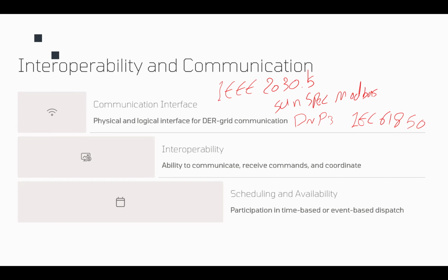Now, we have some functions defined for that in IEEE 1547. So basically, DERs should accept remote commands. It could be active power limits, reactive power settings, or trip and cease commands. Okay, so they also should report their status and some monitoring criteria. Like we said, we are going to have voltage, frequency, active power, reactive power, apparent power, power factor, all of them measured at the point of common coupling, the PCC. All the DERs should report that to the control center, plus their operational state, plus their ride-through events. So if anything happens, like a trip or a protection operating, anything happening at a DER site, they should send that information to the control system and be able to accept commands from the control system.